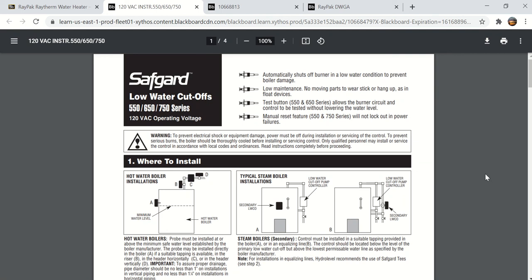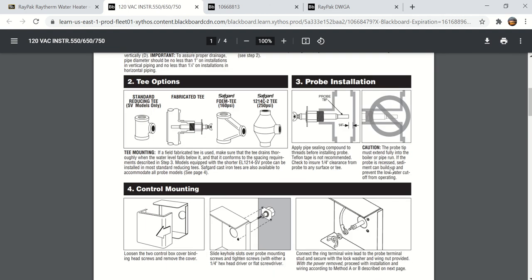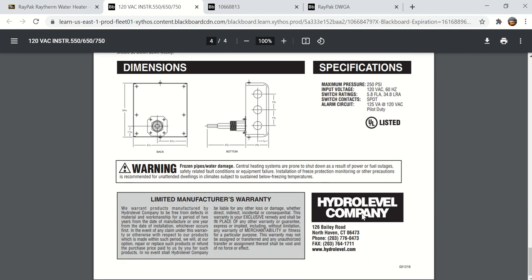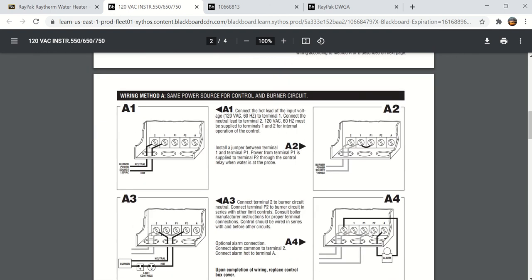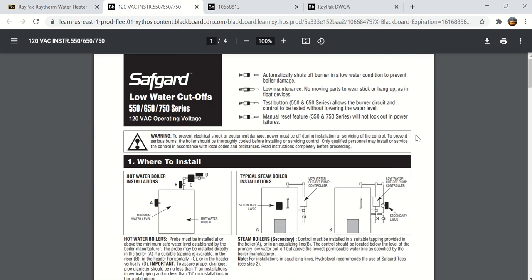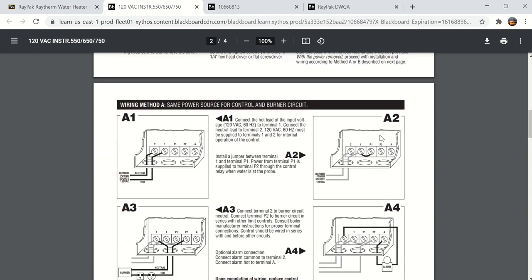Last thing I want to talk about is the Hydro Level Safgard. And I want to do this because I pretty much have told you on everything else that the McDonnell-Miller Model 750 low water cutoff was what they use on, I think, all the other boilers or diagrams that we've looked at. But this one, I know for a fact it is the Hydro Level. The company name is actually Hydro Level Company. I know it uses theirs because when you look at the terminals on the wiring diagram, the pictorial diagram that comes from RayPak, it says that the contact terminals are P1 and P2, and you can see that here.